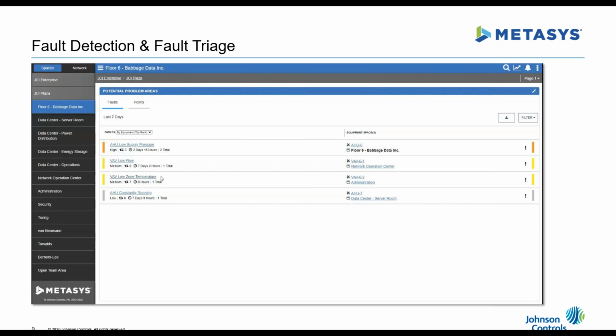Since faults are different than alarms, you won't find them in an alarm summary or with the alarms. You'll see them in the Potential Problem Areas widget. Previously, this widget contained a list of points that were not in a normal status or object status. Now there's a new tab. We have two tabs here: the existing functionality still remains under the Points tab.